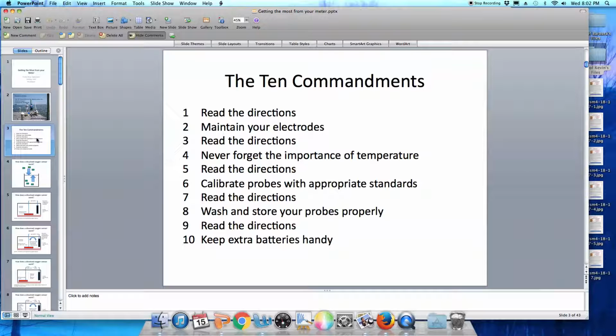You should also calibrate your probes with the appropriate standards. We'll talk about the types of standards for each of these types of measurements: dissolved oxygen, conductivity, and pH. And read the directions. At the end of the day, make sure that you wash and store your probes properly. This will greatly extend their useful life. Frequently, particularly when people are working in brackish water or salt water, not cleaning the probes properly will result in them being heavily encrusted with salt and being damaged.